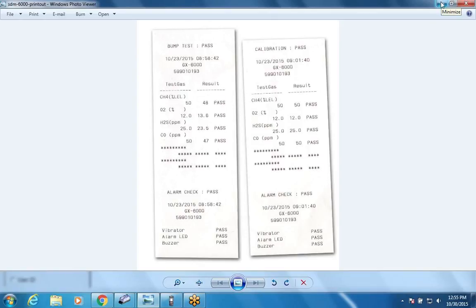Can I just push the alarm check and the cal and it'll automatically do both, or do I have to hit one, wait for it to cycle, then hit the other? No — if you remember in the configuration screen for the bump and cal, there's a setting for auto alarm check. If you have that selected, it'll automatically do the alarm check when you do the calibration or the bump test. If you don't have that selected, you have to do it manually from the main screen.